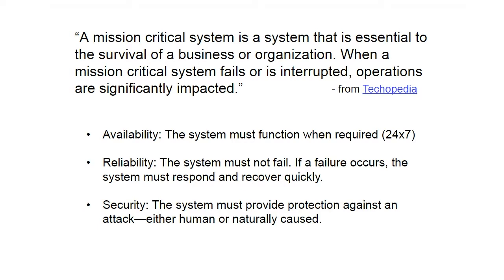So a mission-critical system is basically a system that is essential to the survival of a business or organization. When a mission-critical system fails or is interrupted, the operations are significantly impacted. And there are basically three components to a mission-critical system. One is availability. That system must function when required. It's a 24/7 system. The second is reliability. The system must not fail. And if it does fail, it has to have a way to respond and recover quickly and get back to operating. And the third is security. The system must be protected against attacks, whether it's a human attack, a human error, or even a natural disaster. It has to be protected so that it keeps operating.